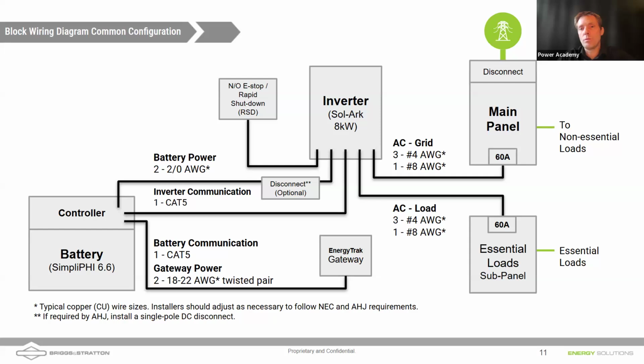And one of the things you have often said about the Sol-Arks is it's nice that they have PCS control. They're rated as a power control system. And so that you don't necessarily have to upgrade your main service panel. You can just limit your output. If your buses are limited to 100 amps, you could limit your output to 20 amps back to the grid. Or if it's a 200 amp main panel, you could limit it to 40 to cover that 120% rule.